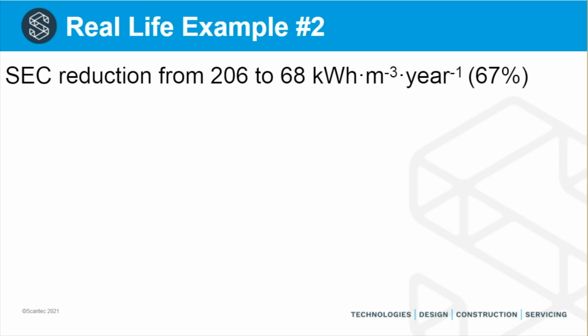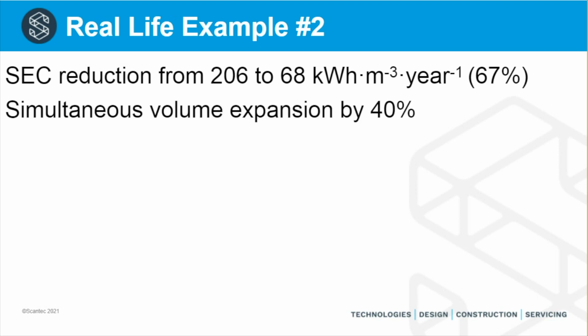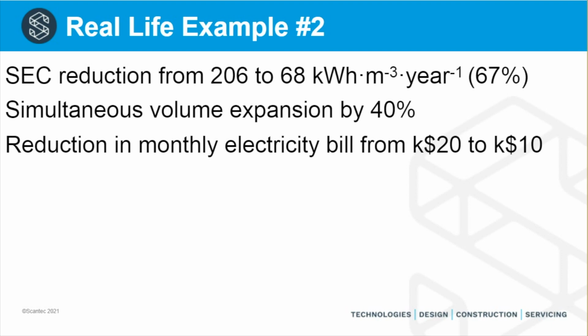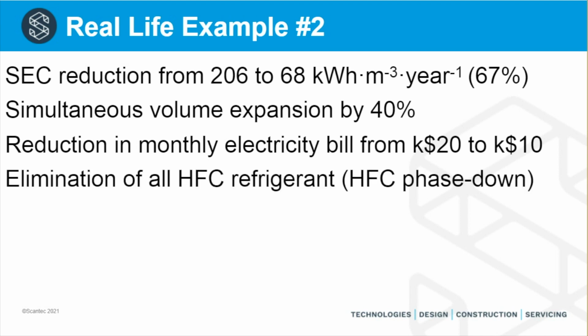And the 68 kilowatt hour per cubic meter value was recorded over a number of months with the SCADA system for the ammonia plant. At the same time that the plant was converted from Freon to ammonia, it was also expanded by 40% to approximately 5,300 cubic meters. Yet the reduction in the monthly electricity bill for the customer was $10,000. Now, interestingly, that reduction in electricity cost per month is enough to pay the installments on a commercial loan over 10 years at 5% per annum to finance the purchase of the new plant.